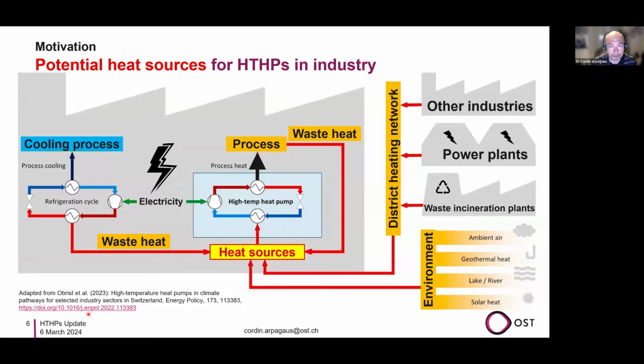So what is the motivation for heat pumps, and especially heat pumps at higher temperature for industrial applications? It's upgrading heat from a lower temperature to a higher temperature by using electricity. Today, an industrial company is typically using a chiller, which is electrically driven, to produce cold for cooling processes. But they are producing waste heat, which typically goes to the environment, and that is useful heat for a high temperature heat pump to upgrade again to higher temperatures.